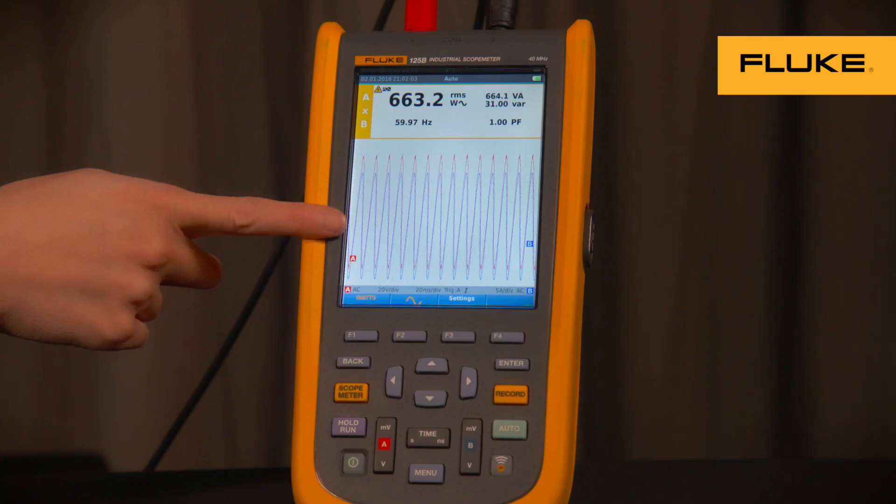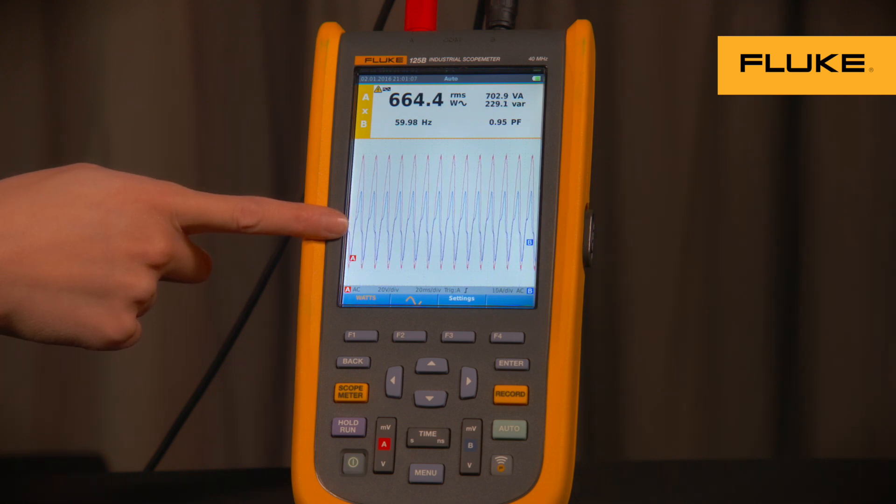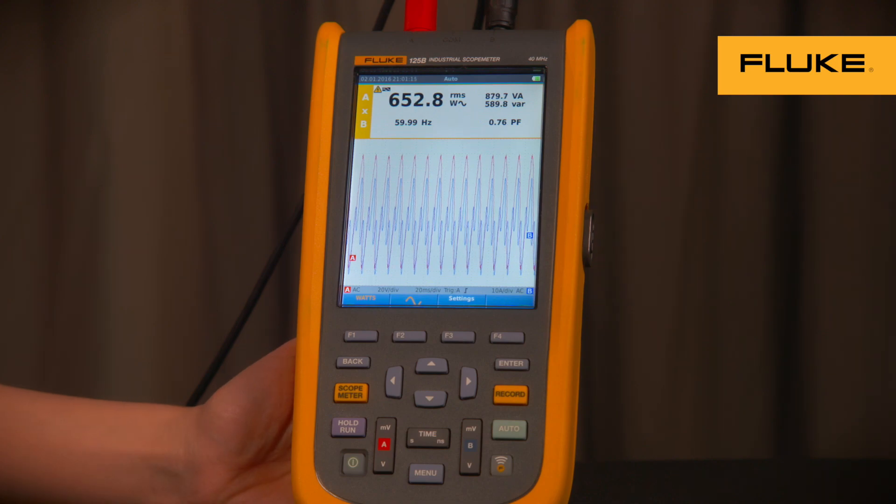If we add a third harmonic distortion on the current, notice the blue sine wave, which is our current measurement, experience distortion. And at the same time, you can see your power factor and all your other power parameters change.